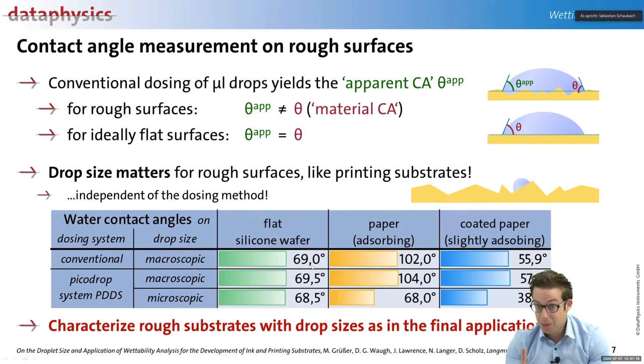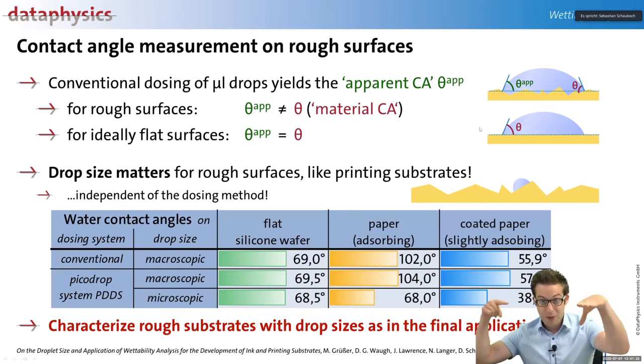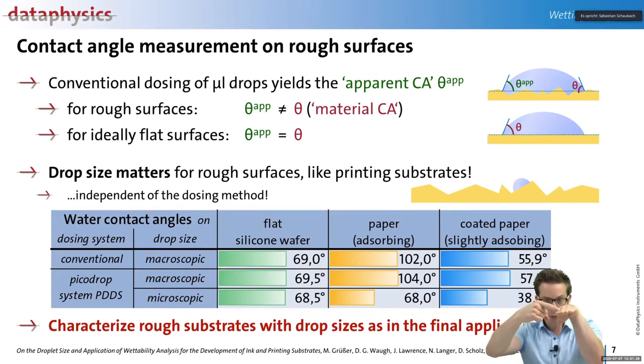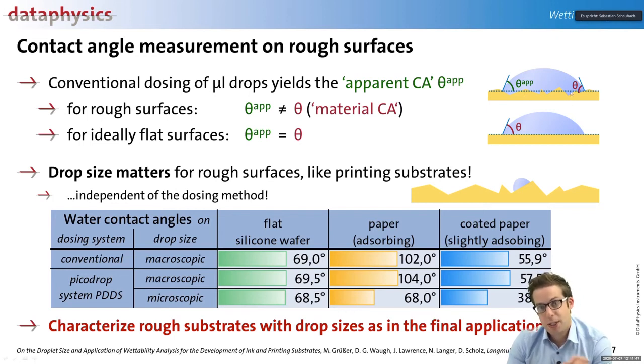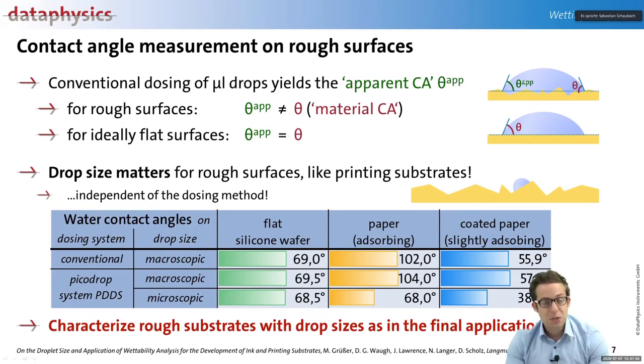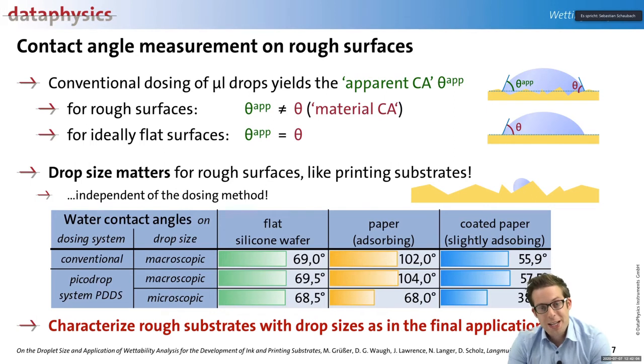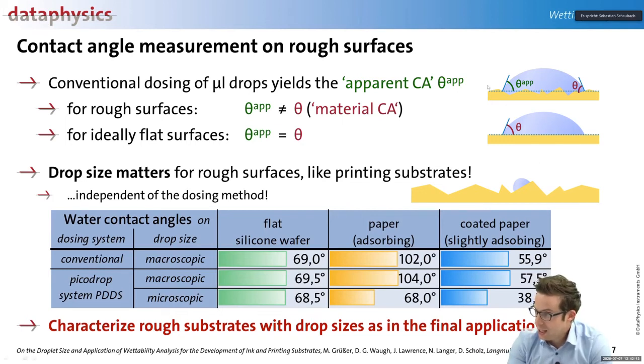Take paper, which is not ideally flat — it has a rough surface. When looking from the side, if there is surface roughness in the plane of the drop, your equipment measures the so-called apparent contact angle. But what you actually need to study your surface is the real contact angle. So if you want to simulate a printing process, you have to push the dimensions of your drops towards the dimensions used in your inkjet process, because then the roughness is taken out of the equation and the drop finds a smooth surface area.